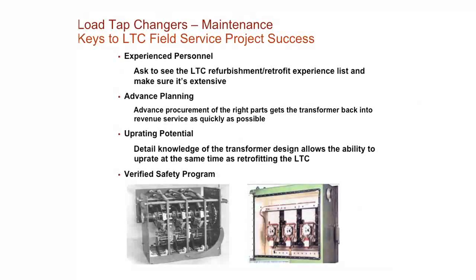So there's another compartment where all the leads, the selectors of the transformer, connect into on this in-tank type tap changer, but it shares the oil with the transformer. This, though, is a separate compartment all of its own called a diverter switch compartment. But you're checking the contacts. The same scenario goes on as with any other type tap changer. You're looking at the linkages, the gears, the contacts.